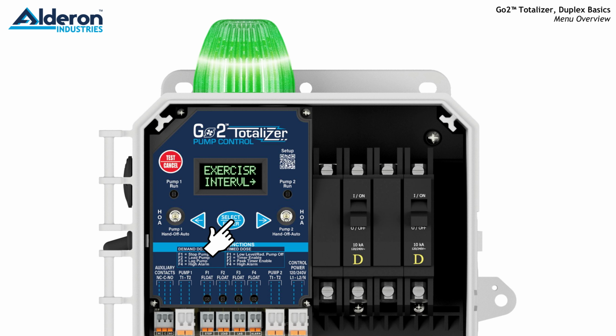Under Exercise Interval, you can run the pump for a programmed period of time if the pump has not run for the programmed off time. This helps keep the pump from locked rotor conditions if the pump has not run for long periods of time. If enabled, for example, you can run the pump for 3 seconds if the pump has not run for 7 days. Minimum is 7 days and maximum is 45 days. Maximum run time is 5 minutes. The factory default for exercising the pump is disabled.